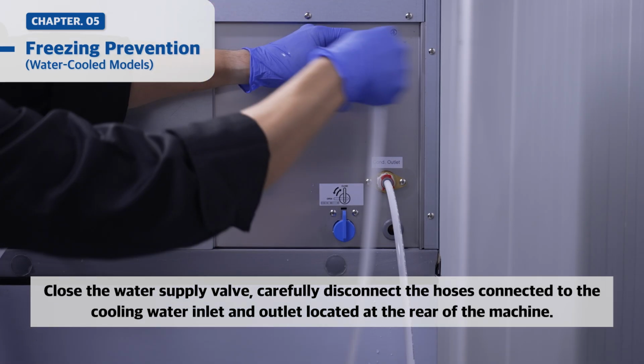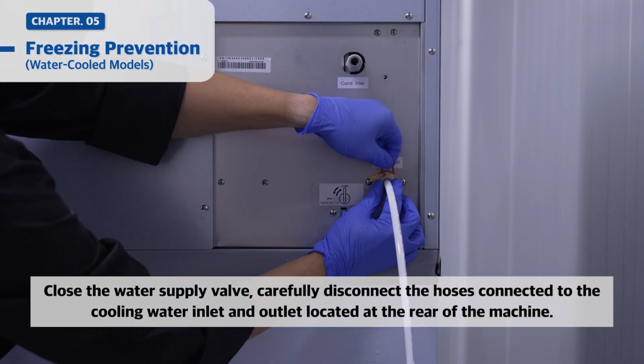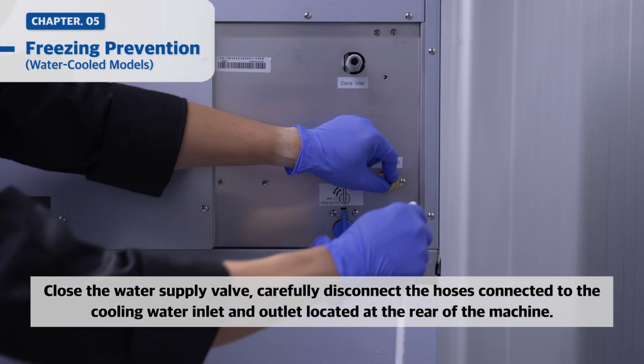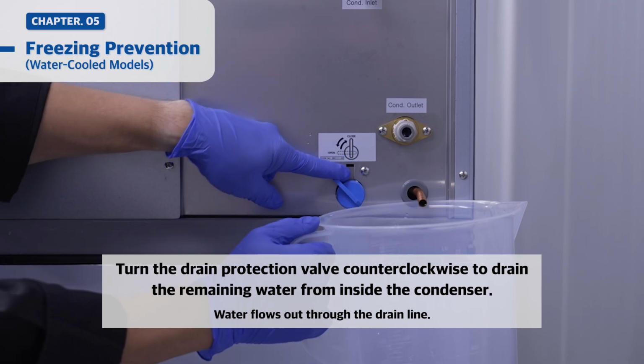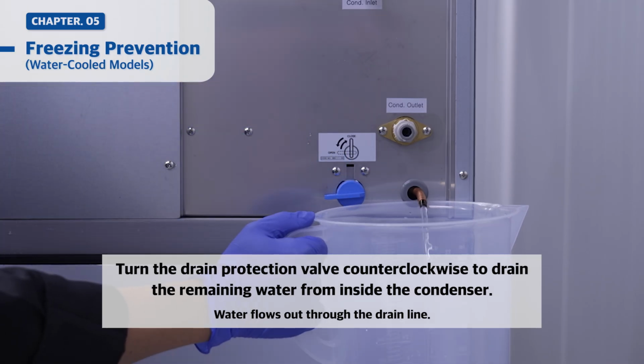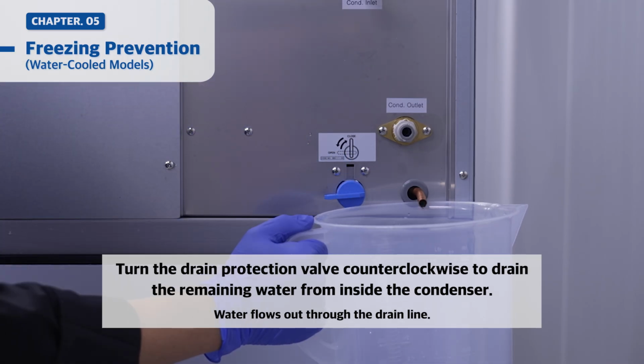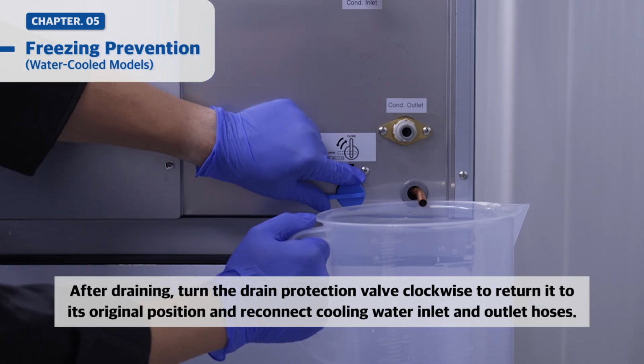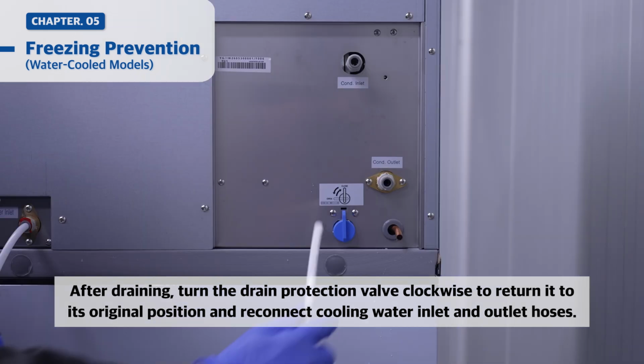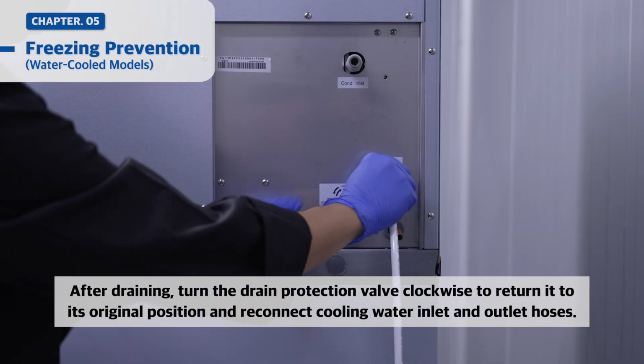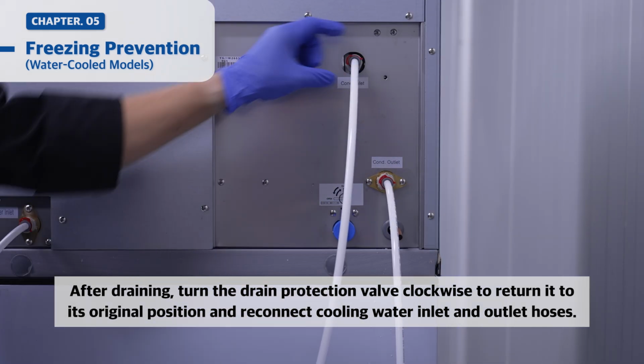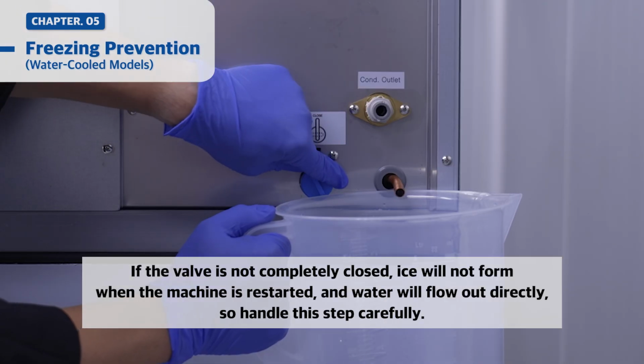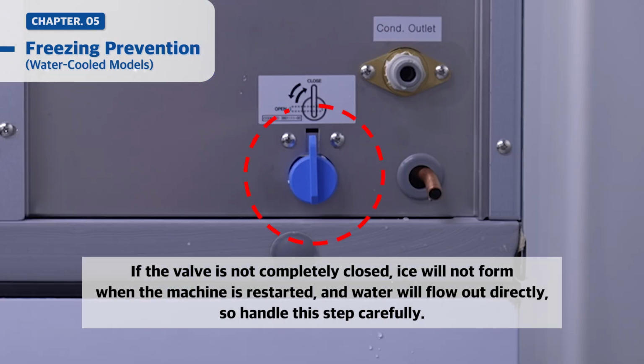Carefully disconnect the hoses connected to the cooling water inlet and outlet located at the rear of the machine. Turn the drain protection valve counterclockwise to drain the remaining water from inside the condenser. After draining, turn the drain protection valve clockwise to return it to its original position and reconnect cooling water inlet and outlet hoses. If the valve is not completely closed, ice will not form when the machine is restarted, and water will flow out directly, so handle this step carefully.